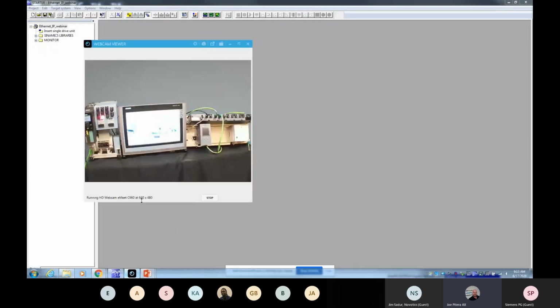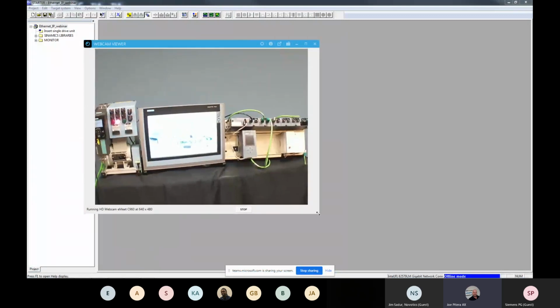Now I have an Ethernet cord plugged in from my PG, my computer, to the switch, and on the switch there's a wire going to the HMI, a wire going to the PLC, and a wire going over to the drive system. And you can see in the picture that the wire currently to the Rockwell controller has been disconnected.